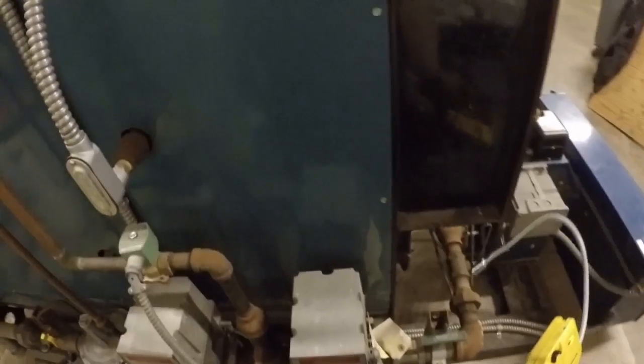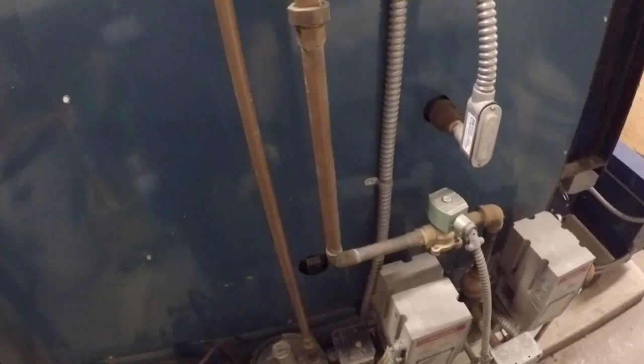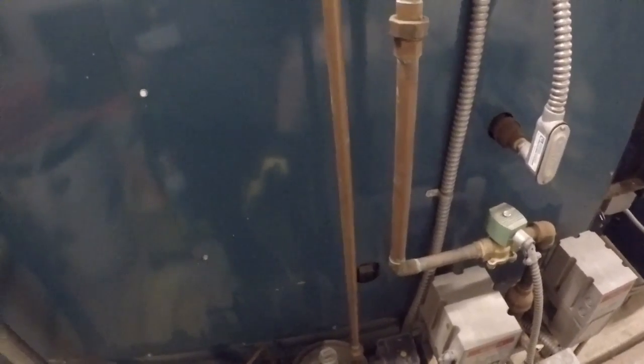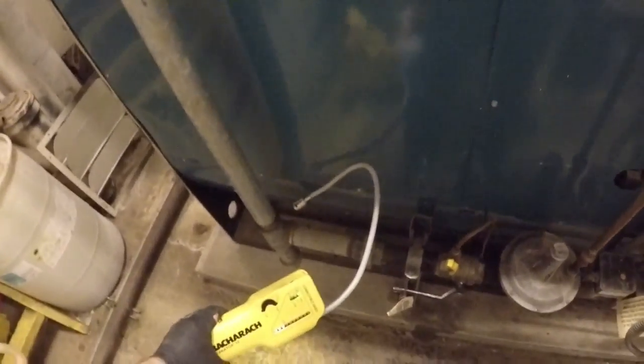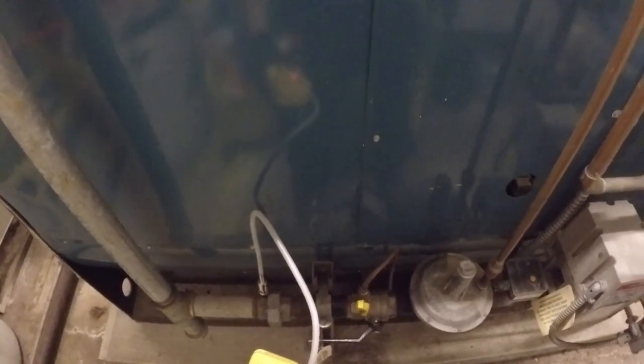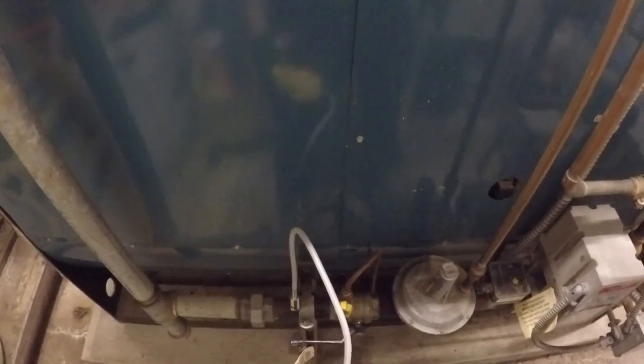It's very noisy. Everything beyond our gas valves is going to be tested at this point. I'm going to test the other side in operation. So listening to the beeps — this is natural gas. Natural gas is going to be lighter than air, so we're probably more interested in what's above than below necessarily.